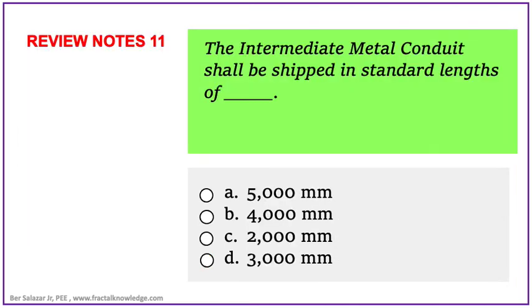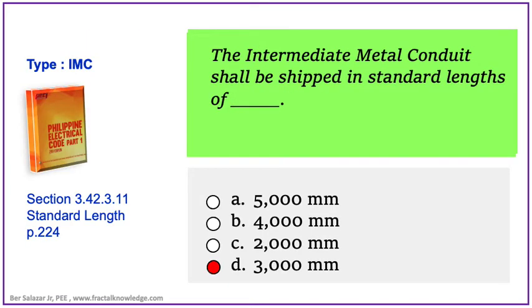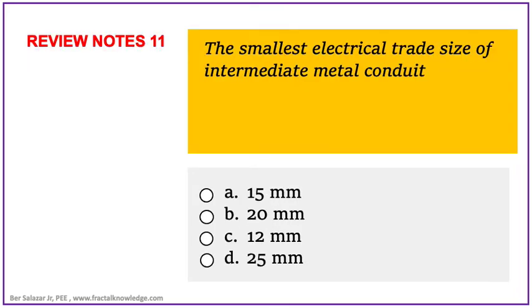The second problem about IMC asks: what is the standard length of IMC? Is it 5 meters, 4 meters, 2 meters, or 3 meters? The answer is letter D: 3 meters or 3000 mm. You can check it in PEC section 3.42.3.11, page 224, for IMC standard length.